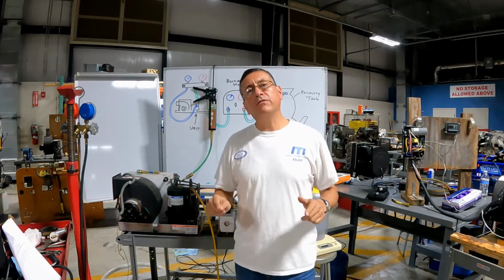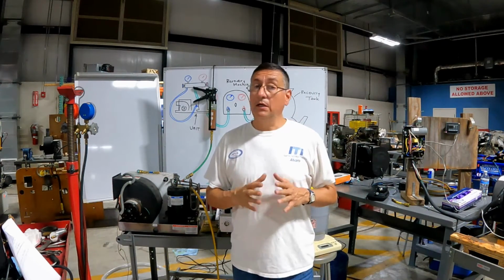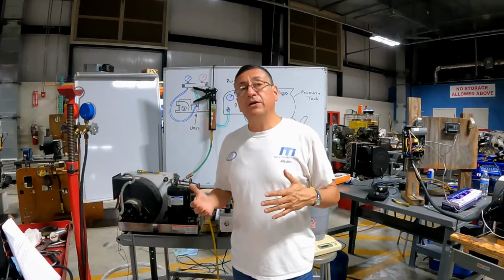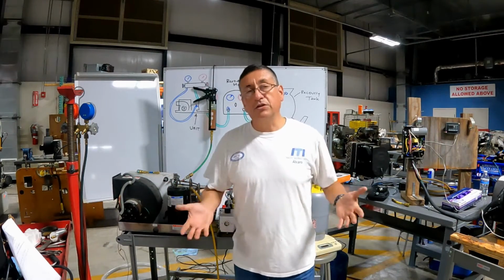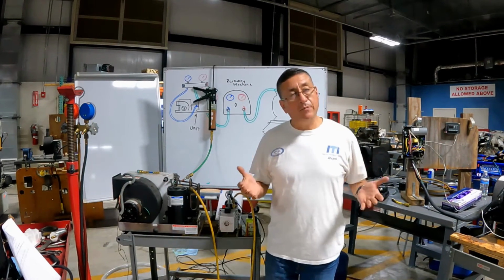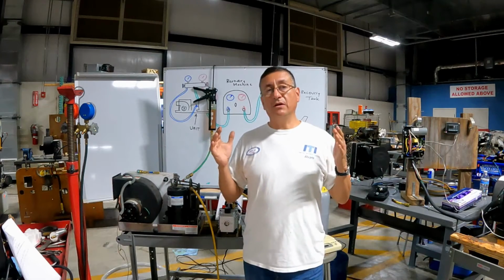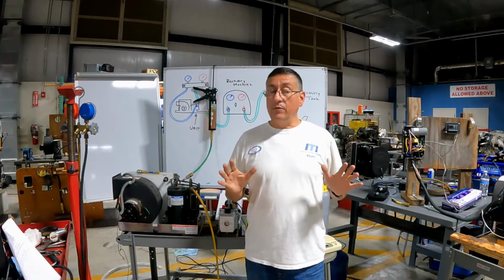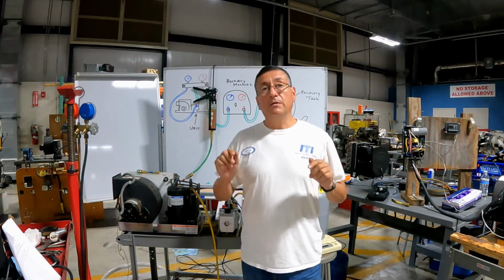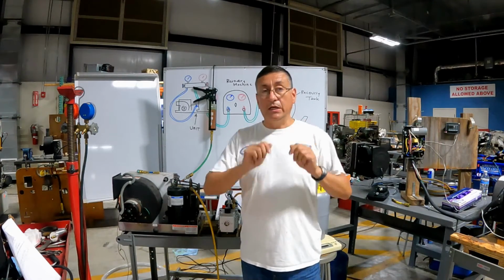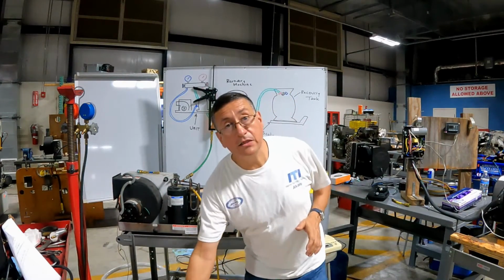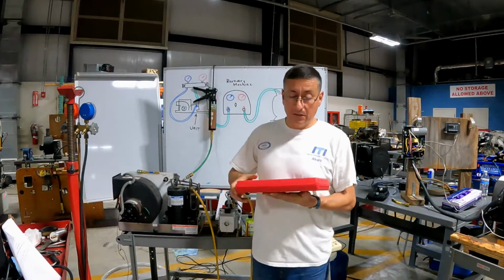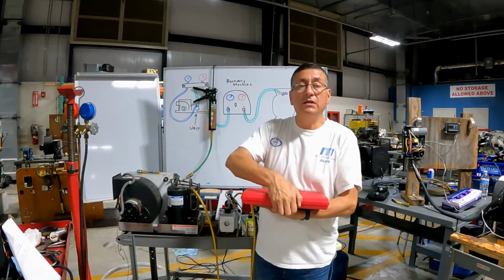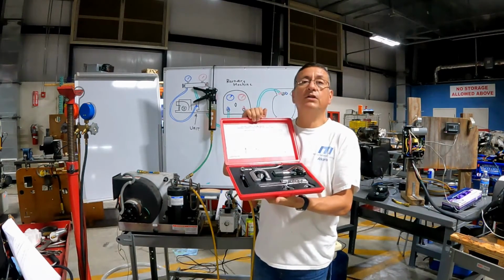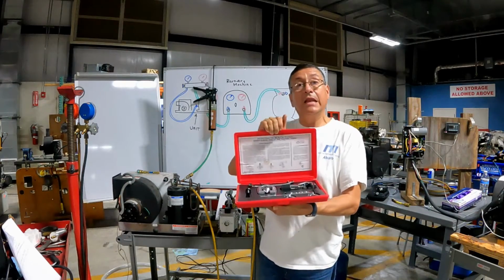As soon as you recover the freon, the refrigerant, now you need to do the reparation. You need to replace the compressor, you need to replace the evaporator, in some cases you need to replace the reversing valve. In marine application, brazing is not recommended, soldering is not recommended. It's recommended to cut the lines and use the flare kit. Use the flare kit in order to repair the lines.